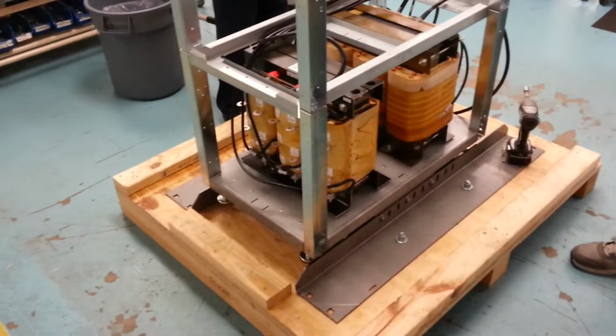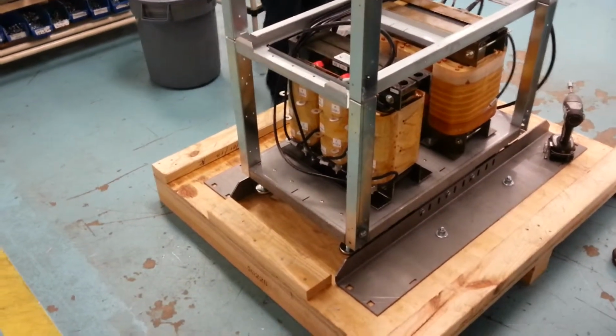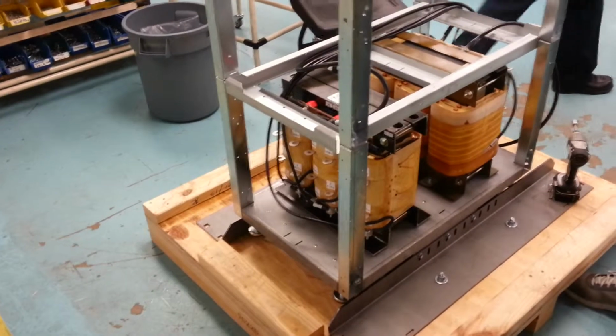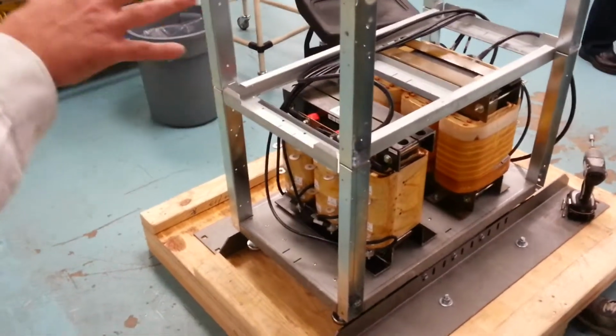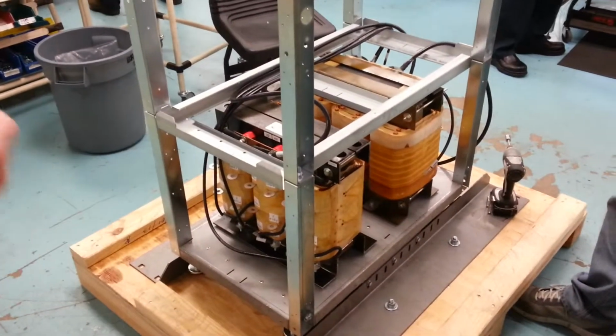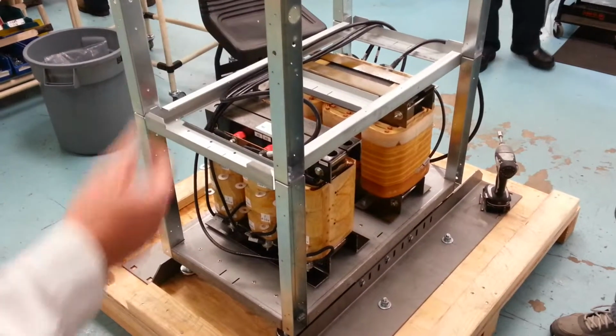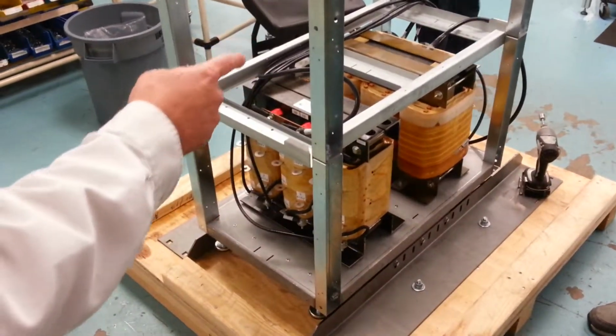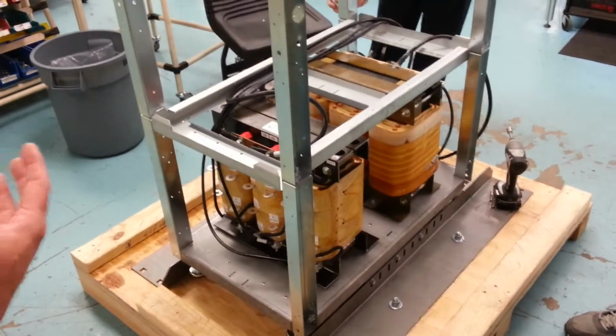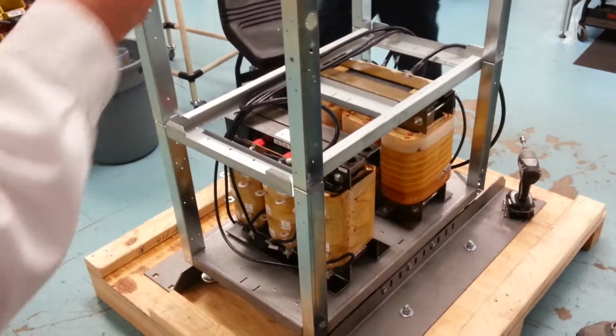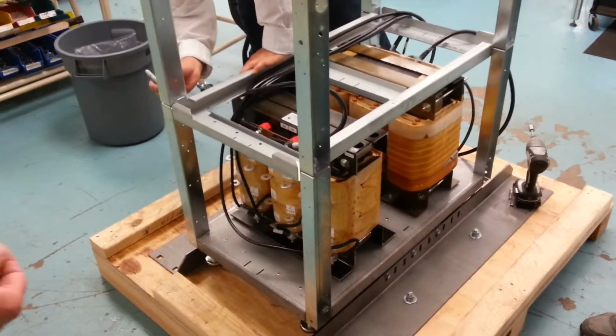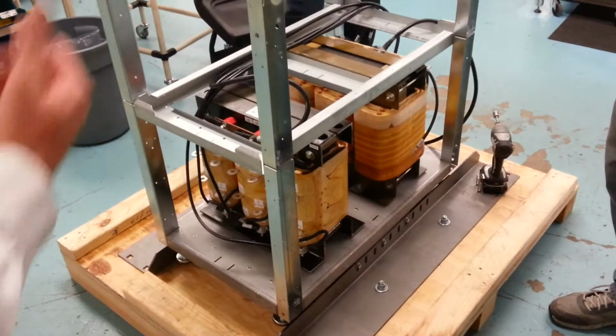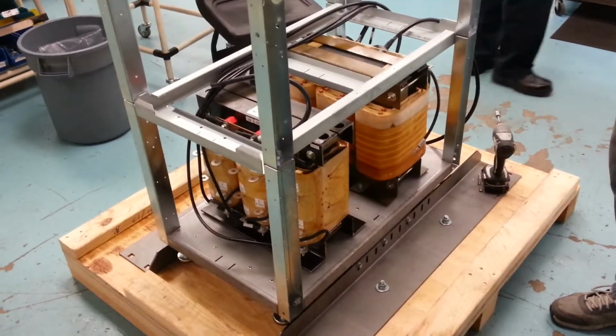That can either have an input or output capacity up to 600 volts. Some of our units will be a nominal, well actually all of them are nominal 208 input, but if the customer wants a different input, different output, we can swap out transformers and they're all multi-tapped. The unit internally is a Y connection, but the customer can have input delta or output Y, depending on the configuration. Of course, in this case, it's an OEM.